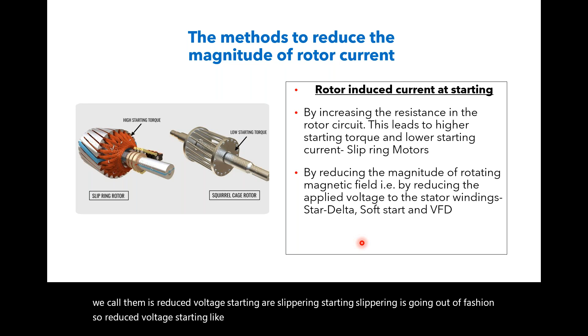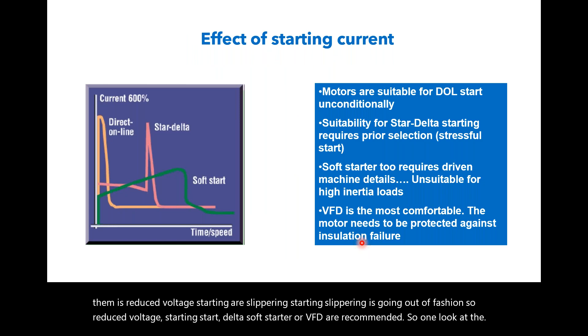Therefore, traditionally there have been a number of designs and schemes for reducing the starting current. Typically we call them reduced voltage starting or slip ring starting. Slip ring is going out of fashion. So reduced voltage starting like star delta, soft starter or VFD are recommended. One look at the typical current will tell you why it is important to go for reduced voltage starting, so as to reduce the demand in current on the transformer.